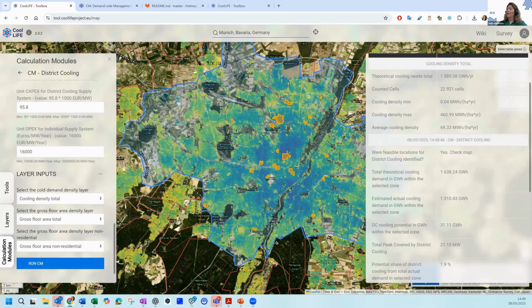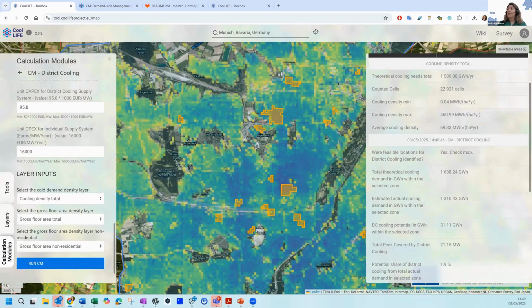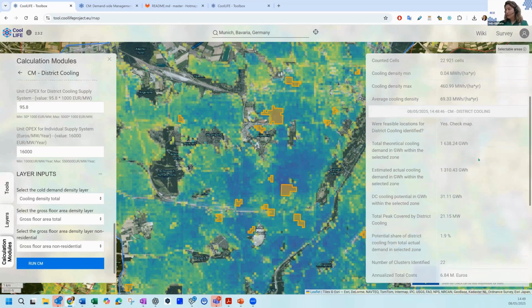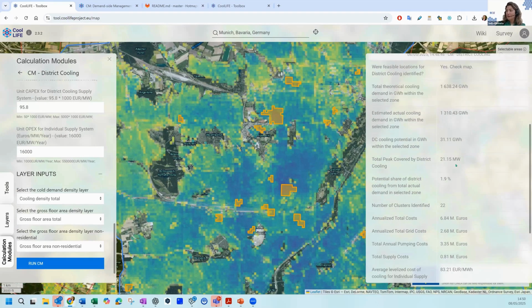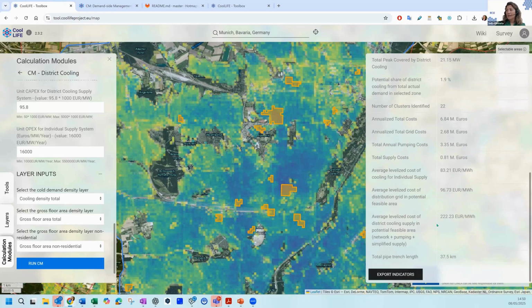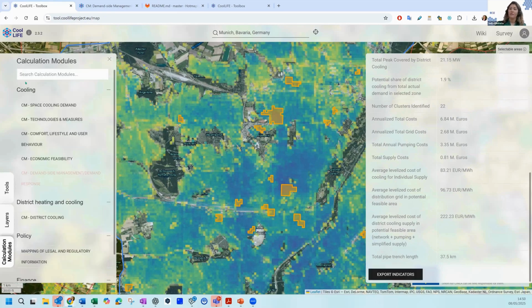Now, what you see here in the map are those boxes that are highlighted in orange. That means that in those areas, the calculation module has found an anchor. Usually that is a healthcare facility, like a hospital, so a structure that has a consistent cooling demand 24/7. And around that, the calculation module identifies other building blocks, visualized as boxes of a hectare per hectare. They are then considered in the assessment of the total theoretical cooling demand and the estimated actual cooling demand, the potential for district cooling and the peak of the area, and then an estimation of the costs and the average levelized cost of supplying the district cooling and of the individual supply.